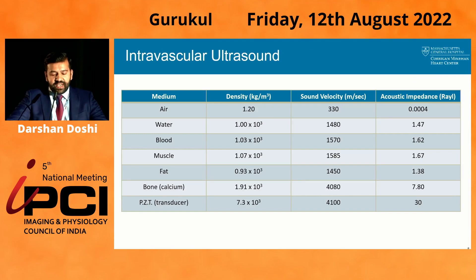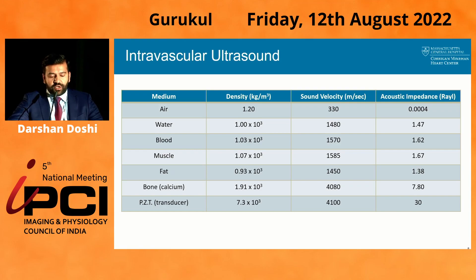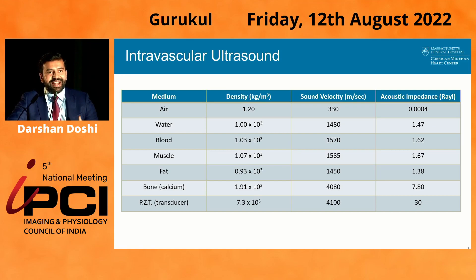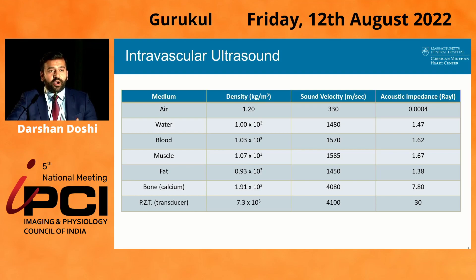How dark or bright something appears is strongly predicated on the acoustic impedance of what you're imaging. Taking common mediums — air, water, blood, muscle, fat, bone, and the transducer element — acoustic impedance equals density multiplied by velocity. Air has the lowest acoustic impedance, so ultrasound waves don't reflect, and air appears black on IVUS. Something with much higher acoustic impedance, such as calcium, produces much greater reflection and therefore appears much brighter.